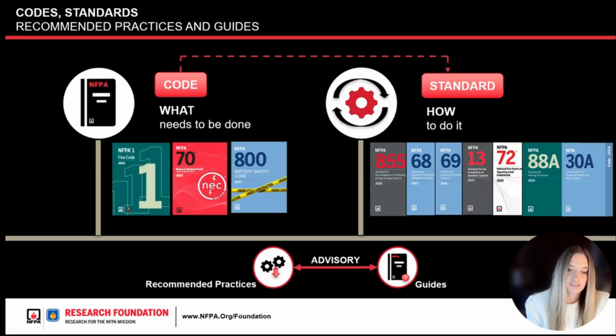Looking at this from the energy transition lens and NFPA's suite of over 300 codes and standards, there are codes that tell you what needs to be done, standards that tell you how to do it, and recommended practices or guides that are advisory in nature. Resources here range from NFPA 1, the fire code, and NFPA 70, the electrical code, to a new project, NFPA 800, looking at the comprehensive life cycle of battery safety. On the standard side, recognizable ones include NFPA 855 for energy storage systems, 88A for parking structures, 30A for dispensing facilities, and the 69 suite for explosion prevention and control.